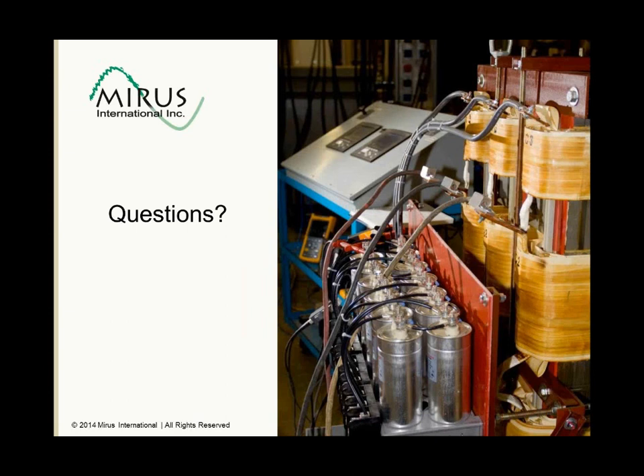A very good LCL filter can block those, but typically the filters are not that effective, and often with active filters or active front-end drives, which also have IGBTs, can introduce problems due to these high-frequency harmonics. And of course, high frequency is not often measured. In the case that I showed, it was just below the 50th harmonic.